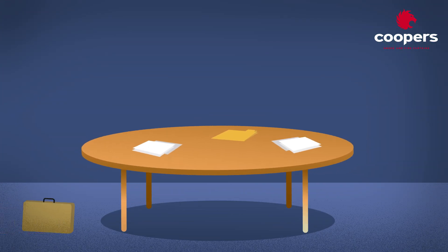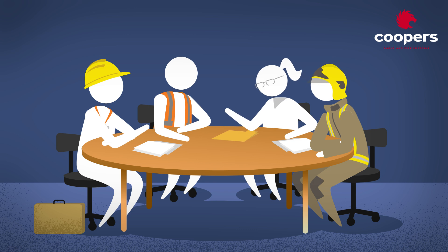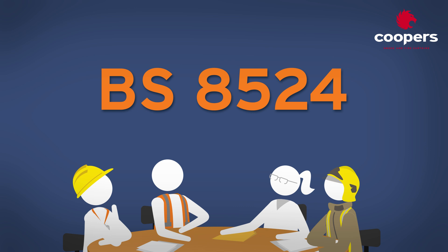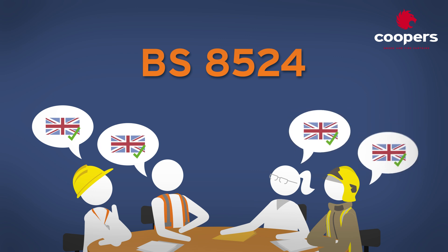With these questions in mind, trade associations, manufacturers, approved bodies, the fire service and others got together to develop a standard unique to fire curtains. That standard is BS 8524, introduced in 2013, which through stringent testing allowed manufacturers to demonstrate that their fire curtain products were able to meet this higher bar set by the UK construction market.